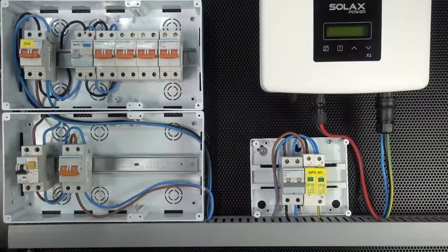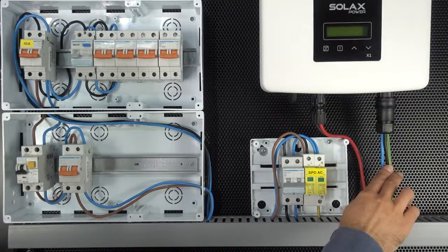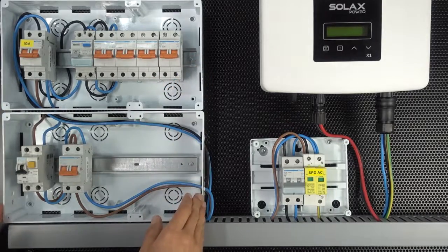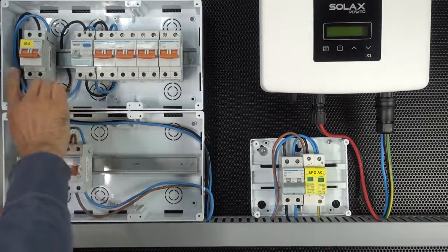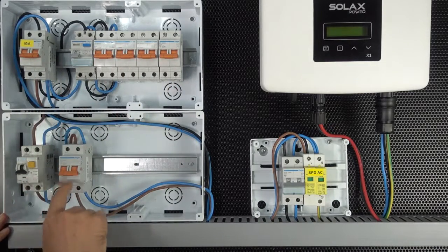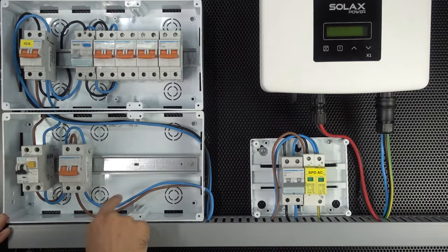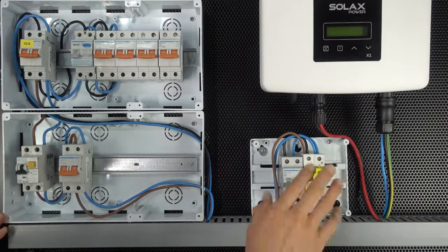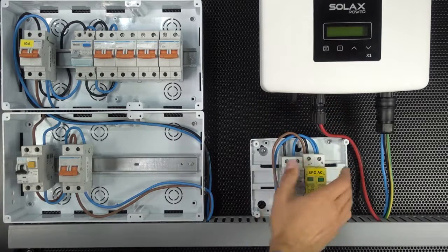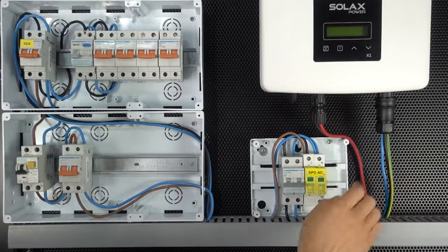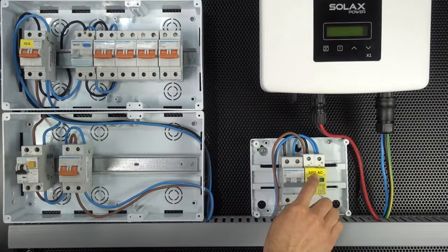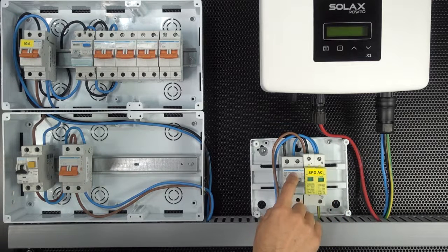Here you can see that we have already connected also the photovoltaic inverter with its protections. This would be the box of protections, the general box of the house where we have the protections for the different circuits, and in addition we have also added the protections that are going to go towards the inverter through this line of phase, neutral and grounding that go towards the other room where we have installed the grid inverter. And we can see that at the alternating current output of the grid inverter, we have connected transient overvoltage protections and a circuit breaker to protect this line as well.